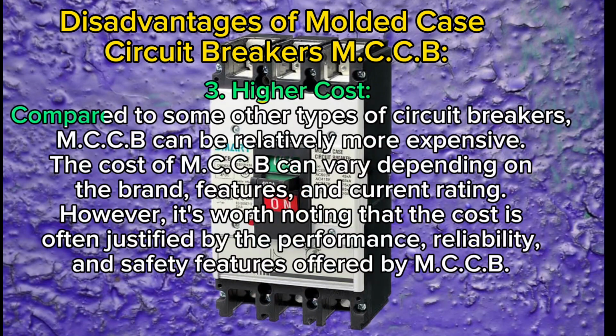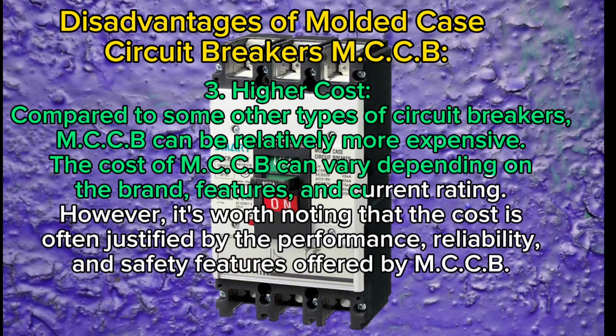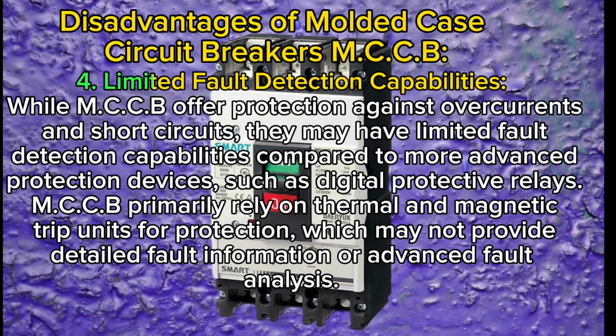3. Higher cost. Compared to some other types of circuit breakers, MCCBs can be relatively more expensive. The cost of MCCBs can vary depending on the brand, features, and current rating. However, it's worth noting that the cost is often justified by the performance, reliability, and safety features offered by MCCBs. 4. Limited fault detection capabilities. While MCCBs offer protection against overcurrents and short circuits, they may have limited fault detection capabilities compared to more advanced protection devices, such as digital protective relays.